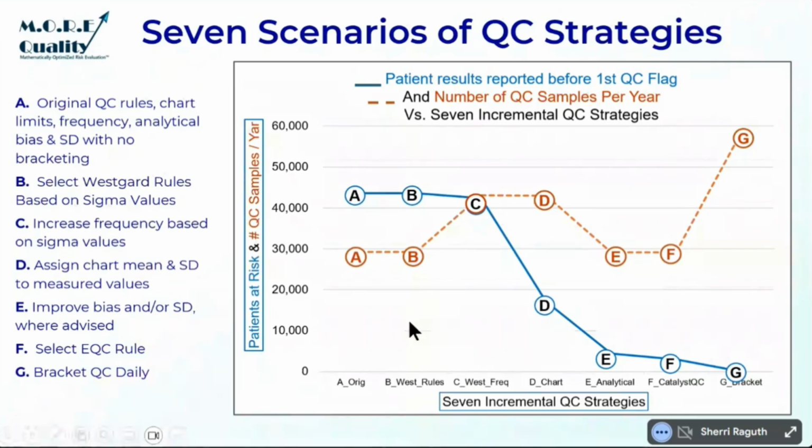This process with our software will report far fewer errors. So this is what you were doing with Westgard's recommendation, exposing 40,000 patients to risk. With ours, you're down to about 3. And if you want to bracket your QC, you can reduce it to 0. We have a better process than Six Sigma and Westgard rules. And it's not a separate process. It's a process that layers on top of whatever you're doing for quality control now. Is that not right? Exactly.